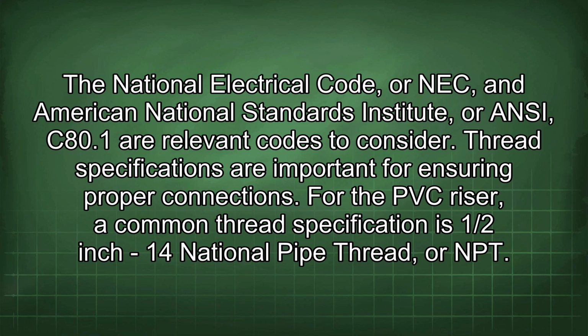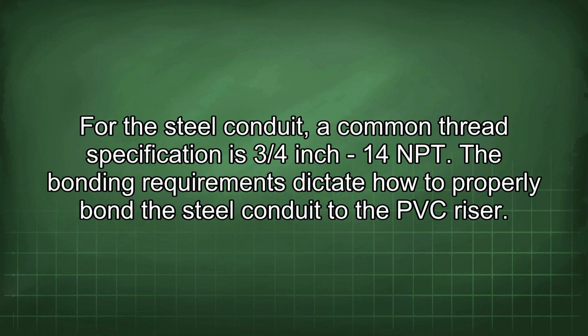The National Electrical Code, or NEC, and American National Standards Institute, or ANSI, C80.1 are relevant codes to consider. Thread specifications are important for ensuring proper connections. For the PVC riser, a common thread specification is 1/2" 14 National Pipe Thread, or NPT. For the steel conduit, a common thread specification is 3/4" 14 NPT.